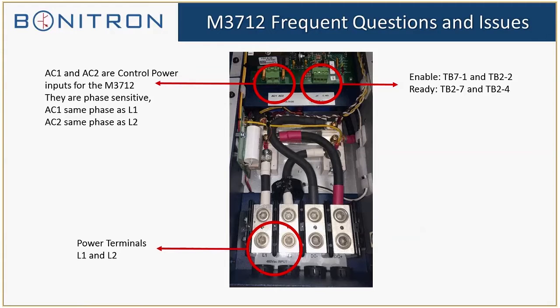The AC1 needs to be the same phase as L1, and AC2 needs to be the same phase as L2. Otherwise, you will get that undervoltage fault that I discussed about two slides ago. In order to get anything out on the DC terminals here, there needs to be an enable on this terminal here. This terminal is just a simple 4-pin terminal. The two terminals on the left, TB7-1 and TB7-2, are the enable. And by and large, customers just put a simple little jumper wire here, and the unit's enabled all the time, and it's ready to go. It's ready to give DC power to the drive.